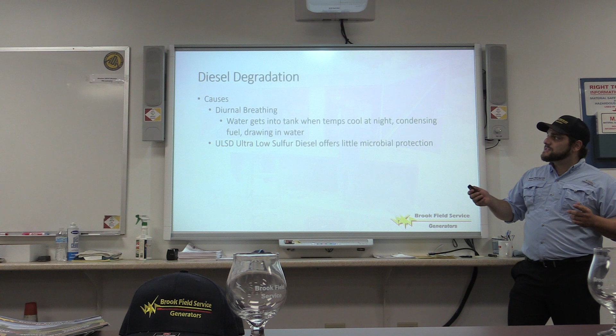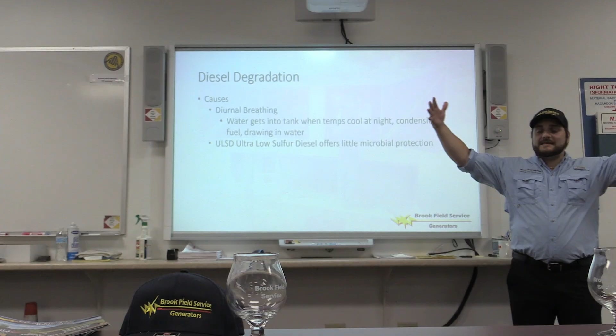So further on this, one of the main causes of diesel degradation is called diurnal breathing. Water gets into the tank when temperatures cool at night, causing condensation, bringing air into the system, and obviously air has a good chunk of water in it percentage-wise, which condenses into the tank.